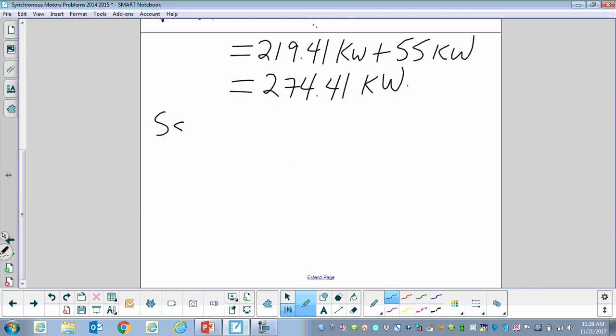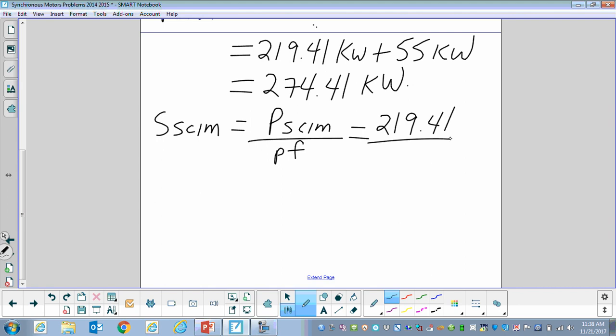S of the squirrel cage induction motor equals power of the squirrel cage induction motor divided by power factor. Taking 219.41 divided by 0.75 gives us 292.546 kVA.